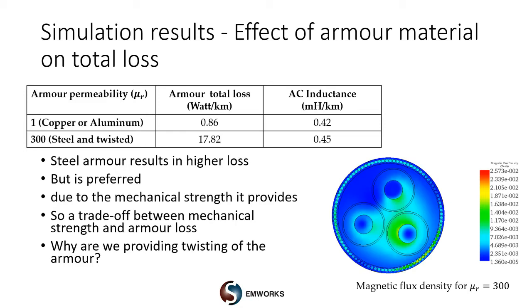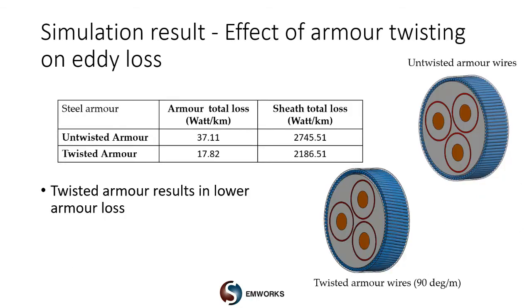Next, let us see the fundamental reason why we use twisted armor. Notice the two figures here — the top right shows untwisted armor, and the bottom shows twisted armor wires. We established that we will use steel for armor wires despite the higher loss because it provides better mechanical strength. Simulation showed what kind of losses occur with untwisted steel versus twisted steel armor. Twisted steel armor results in much lower armor loss, and that is really why we use twisted armor wires to fabricate these cables.